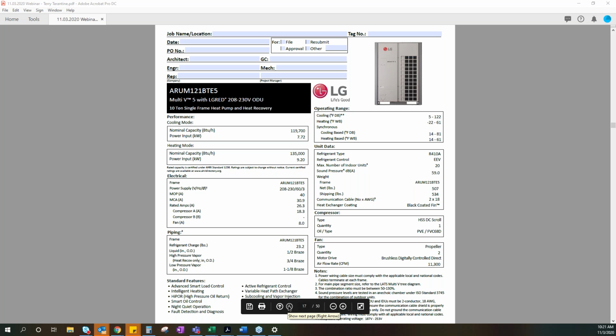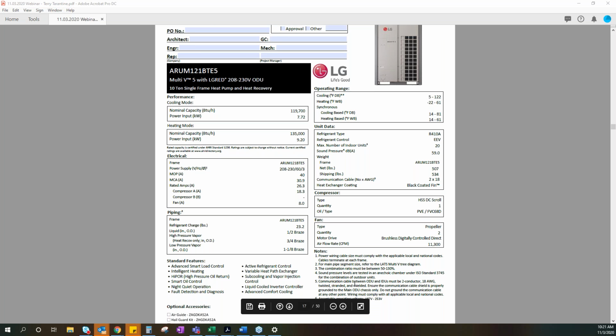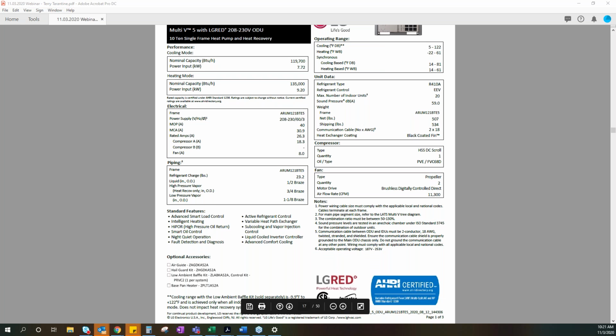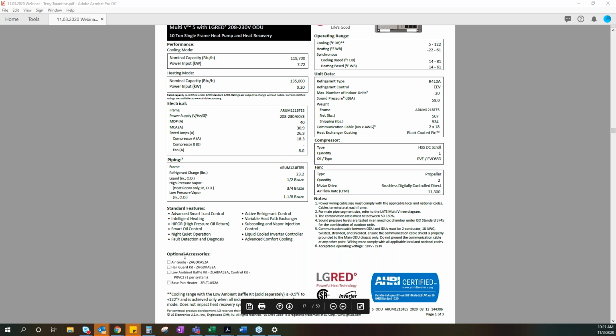We go to the bottom of the page where there's some accessories. A couple of things I do want to point out. You'll notice on the left, optional accessories, there is a low ambient baffle kit available. We can run these in critical cooling applications where we'll get full cooling capacity down to 0 degrees. And then we also have a base pan heater. The base pan heater is very important in that we are running heat pumps below 0 degrees outside. So they will frost up, and we run defrost cycles. The base pan heater is there to make sure that we don't freeze the condensate water in the base pan. We want to make sure that that water drains out completely.